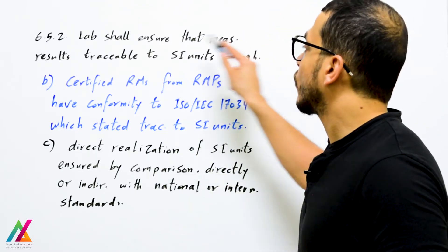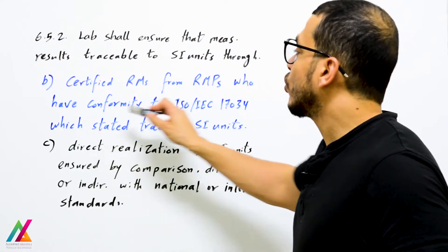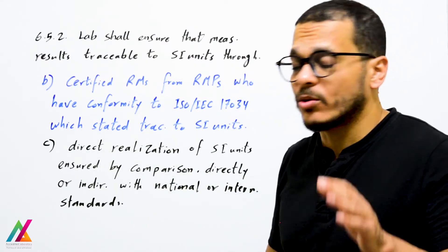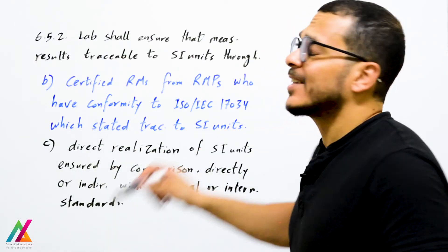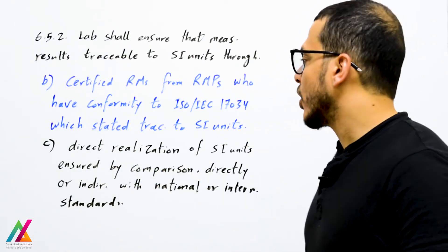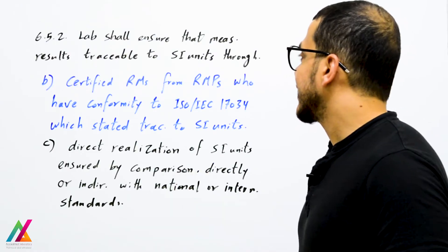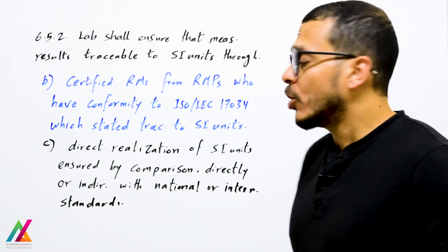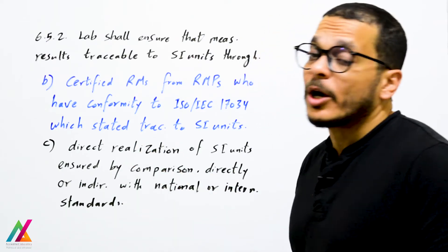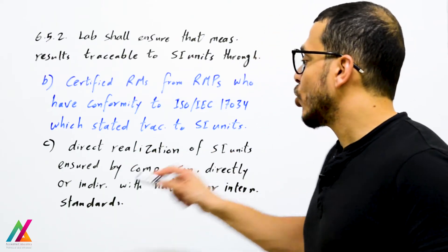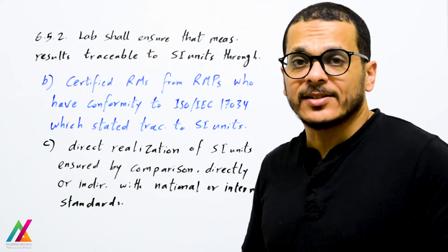To ensure traceability of measurement results to SI units, CRM shall be provided from reference material producers with conformity to ISO/IEC 17034, which states traceability to SI units. The last option is direct realization of SI units, ensured by comparison — directly or indirectly — with national or international standards.